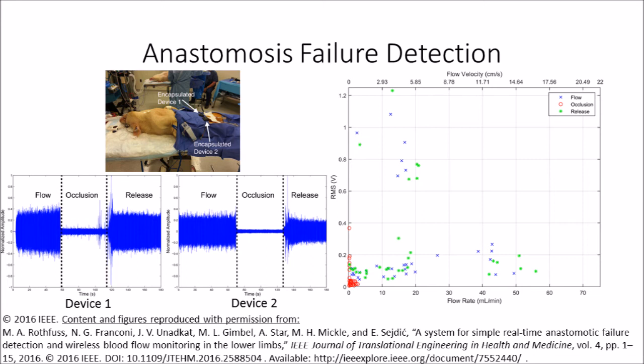The results of this data collection showed flow waveforms with an average amplitude standard deviation 3 times greater than that of the occlusion case. Establishing the baseline flow waveform amplitude compared to the occluded waveform amplitude simplifies interpretation for operators and provides an easy-to-interpret indicator for vessel patency. The high false positive rate found with the gold standard in free flap monitoring, particularly in the peripheral veins, can be reduced using the system developed in this research, which eliminates the problematic wire tether.